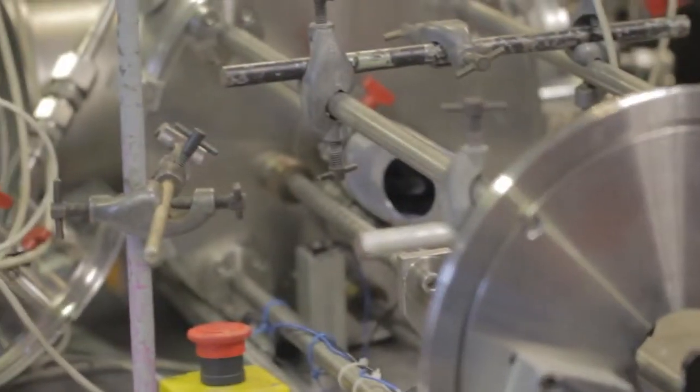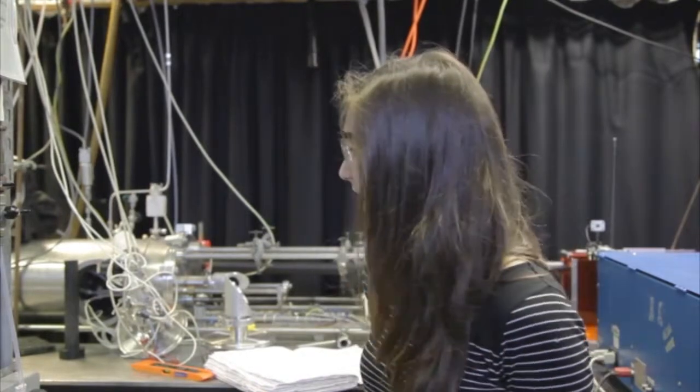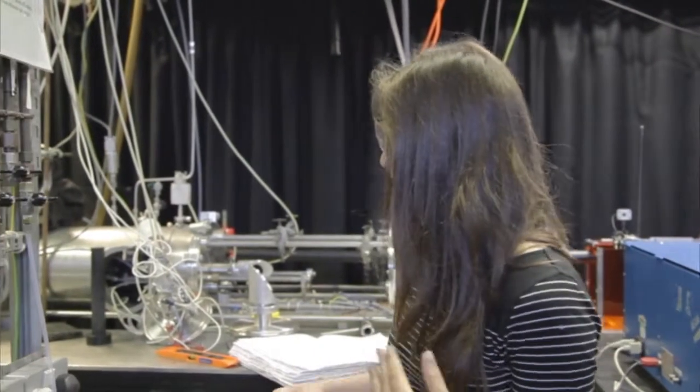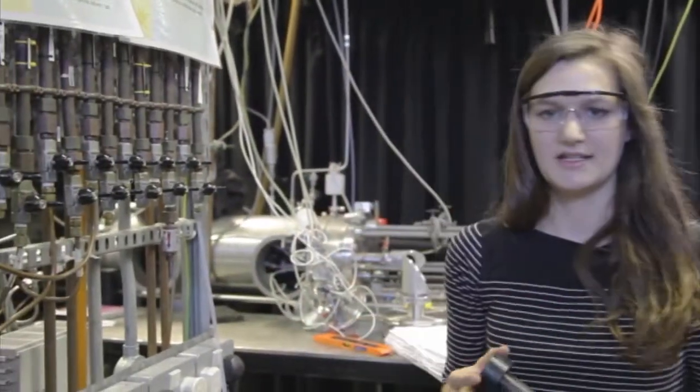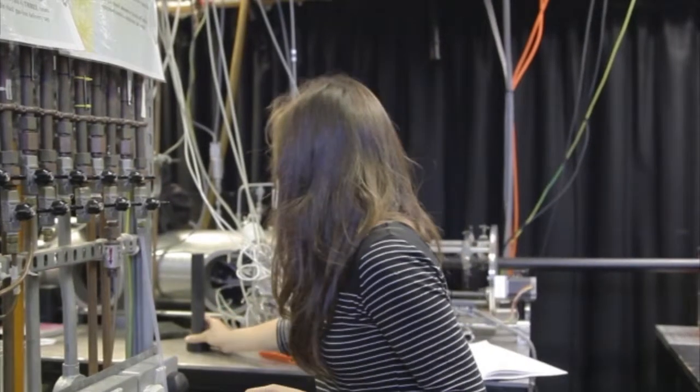We've also got some thick black laser curtains, which ensures that if we're aligning, which I am doing at the moment, that no light can bounce off anywhere. So the alignment process, we use bits of paper to see where the laser's positioned as you look down the chamber. We also have alignment tools such as this black tube and some circular bits of paper with holes in, which guide us towards the centre of the chamber.